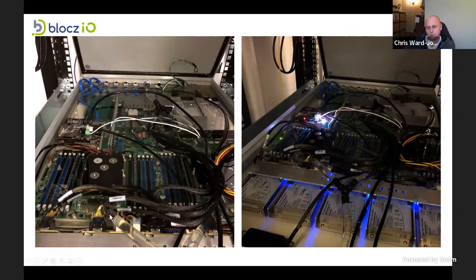We have a variable speed pump here, which picks up the coolant, the liquid in the chassis. It distributes it through this pipework, which goes to this heat sink on the CPU, and there's another heat sink just over here behind these cables on another CPU. Then you can probably just make out the pipework coming back from those heat sinks, which we extract out of the back of the chassis into a heat exchanger.